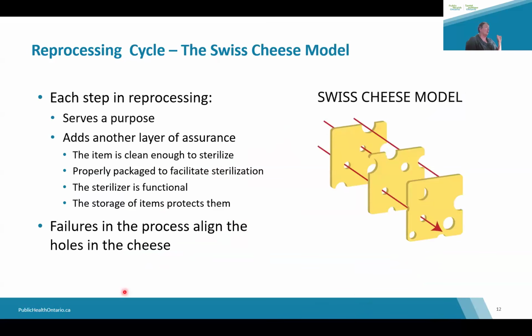So when we look at our reprocessing cycle, think about the Swiss cheese model. Each step in reprocessing serves a purpose, and we briefly touched on those purposes. Each one adds another layer of assurance. Is the item clean enough? That's one level. Was it packaged properly to facilitate sterilization? That's another level. Was the sterilizer functional? That's another level. And did you store your items so that they're protected? Another level. And if you have any failures in the system and those little holes all line up, then you're going to end up with an unsterile product and a risk of transmission of infection to your patient.